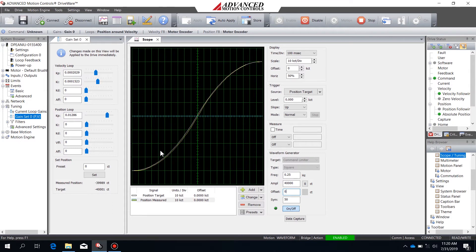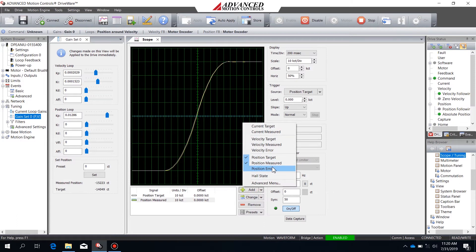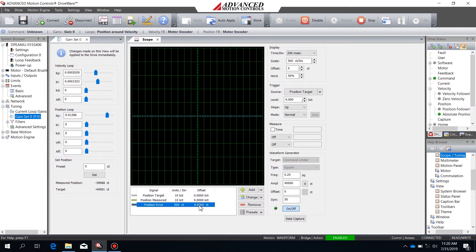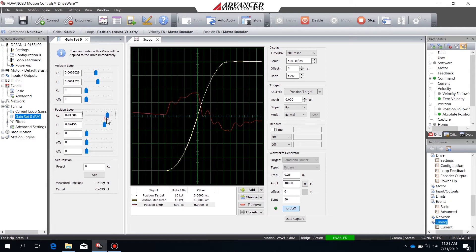Before I change any gains, I want to make sure I have stability at zero velocity as well, so I'll change the time per division so I can see both sides of the waveform. I'm also going to add the position error signal to see in more detail where any error is occurring. The majority of error is at that constant velocity section. I'm going to use the integral gain to try and get rid of that error and make the error balanced around zero. Once it's mostly balanced around zero counts, I can increase the proportional gain some more to further reduce the error.